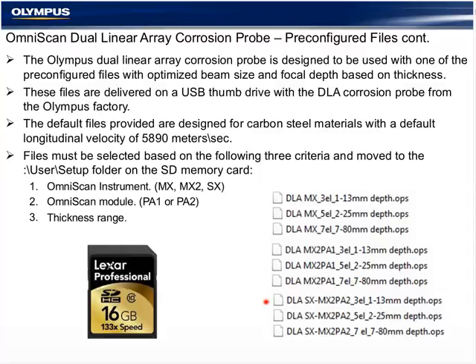The thickness range is a modification in the wedge delay and setup of the gate position and color palette for three ranges, of which the overwhelming majority of the thicknesses for corrosion mapping that we see at Olympus would be the 2 millimeter to 25 millimeter depth here. And again, these are copied from the USB flash drive that comes with the probe to the user setup folder on the SD memory card.